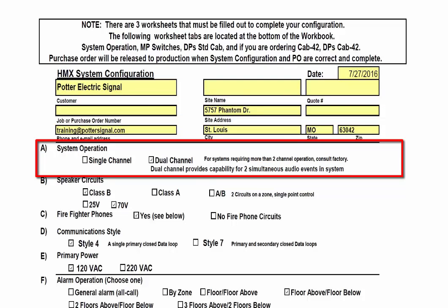People often confuse multiple messages with multiple channels. Both single and dual channel systems are capable of sounding multiple messages. The difference is single channel can only sound one message at a time, while dual channel systems provide the ability to sound two different messages simultaneously. Dual channels are most often utilized in high-rise buildings when there is a requirement to sound an evacuation message on certain floors while a different alert message sounds throughout the remaining floors.